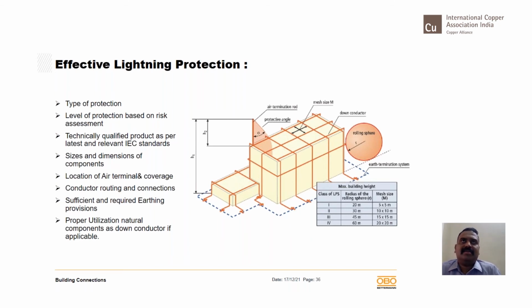Because in many installations, when it is contracted and they use a local component available in the market, sometimes these components may not have been tested for that particular high energy. So obviously there are chances of splitting or damage to the equipment. Then the size and dimensions of the components are very critical, especially the conductor and the air terminal. The standard defines a specific size for every conductor that is to be used. The options are available in 62305 Part 3.